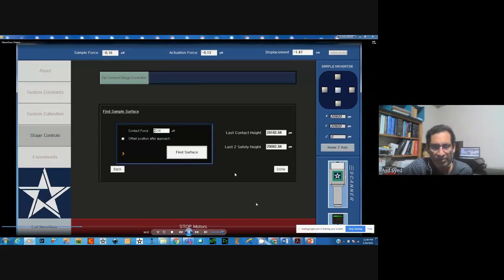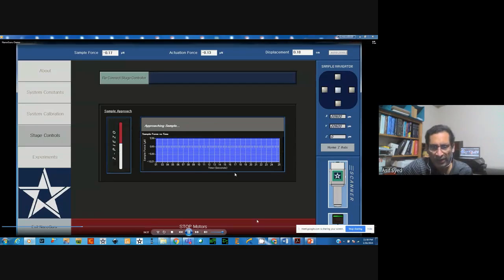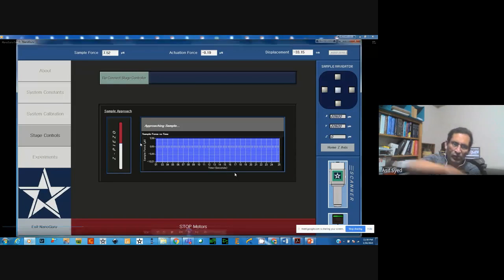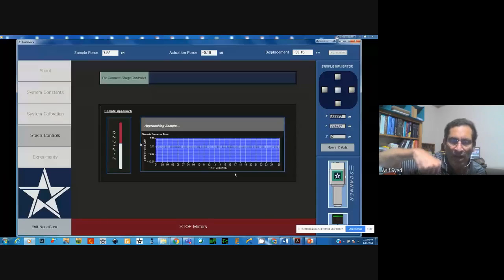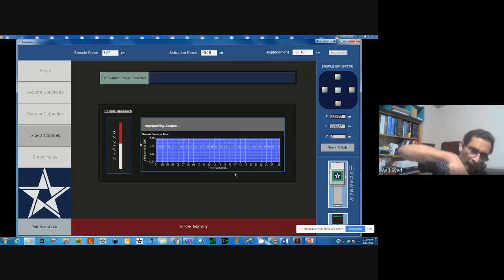Now when you press find sample, you can see there is a window here. It shows you where the piezo is. Right now it is at the middle, but as you want to approach and make contact, we extend the piezo with the transducer, and with the extended position we approach the sample surface. The idea is that when the piezo is extended and the tip makes contact, we can pull the piezo back quickly so that it is away from the surface, or makes contact with the required force that we need. That is why we extend the piezo and approach the sample surface slowly. As soon as the tip makes contact, the piezo immediately pulls the transducer away from the surface. You can see that here.